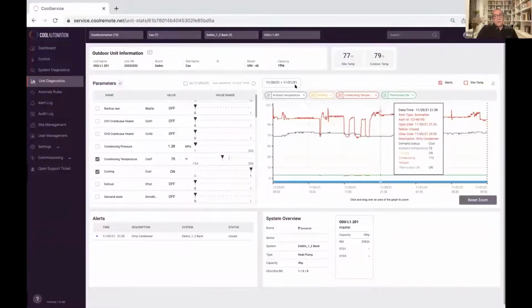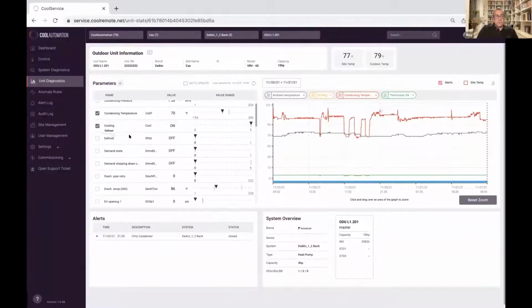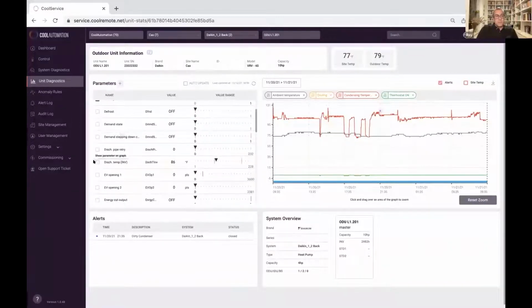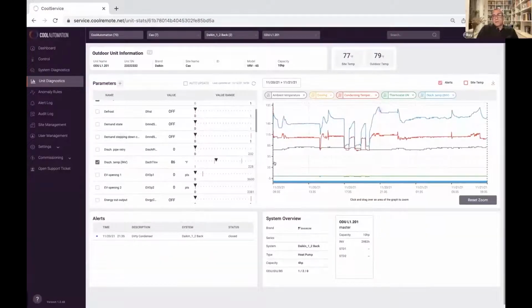So I want to take a look, maybe at another parameter of interest—let's check the discharge temperature, see if it's high. I can see that it is high, not high enough to require me to go on site, but it's a good idea to keep monitoring it and see if it happens again. If it happens again in a short period, maybe it requires me to travel on site, or ask somebody else to go check the roof.